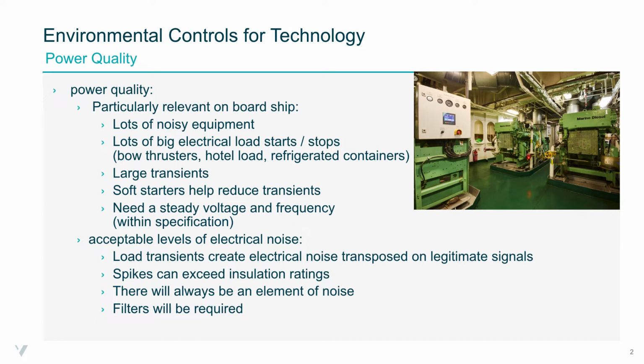So why is this a concern? Electrical noise can find its way into electronic equipment that operates using very small signal voltages. Noise induced into a piece of equipment can transpose a fake signal on top of a legitimate signal, causing malfunction. These induced voltages can also exceed the insulation rating of components within technology, resulting in outright failure.